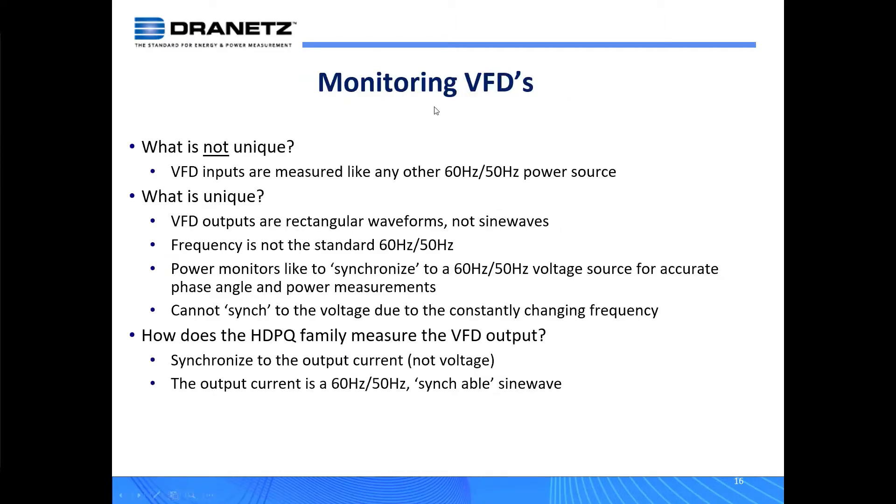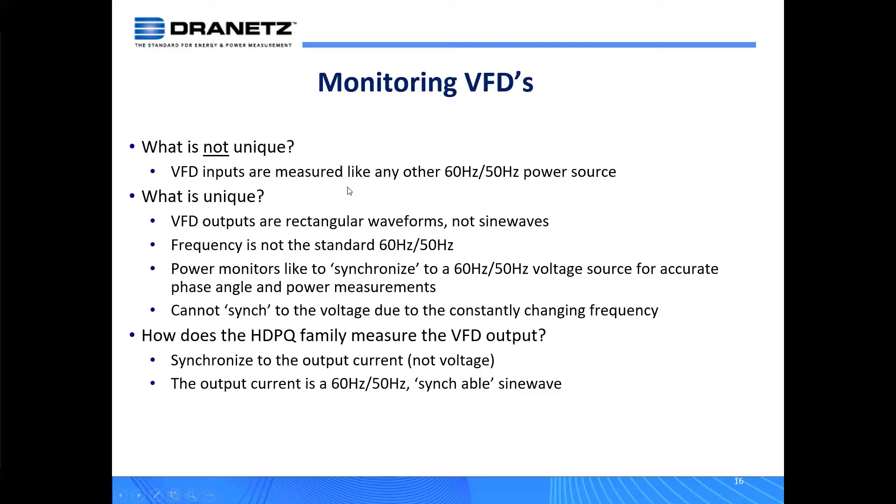So what are the topics on monitoring VFDs? First of all, what is not unique? When we're looking at the input of a VFD, it's measured just like any other 50 or 60 hertz circuit. So the input of a VFD is not a challenge for any prior Dranetz products, HDPQ, or most power analyzers.